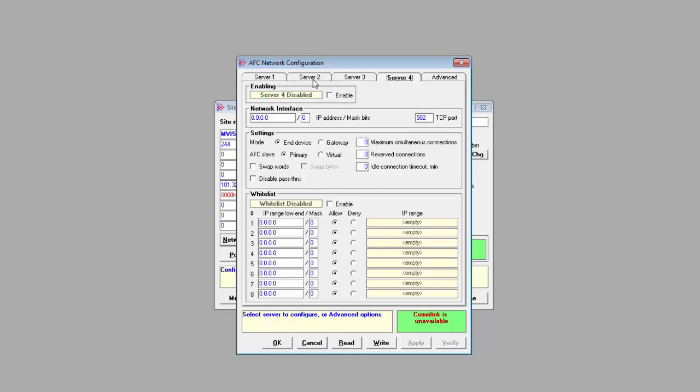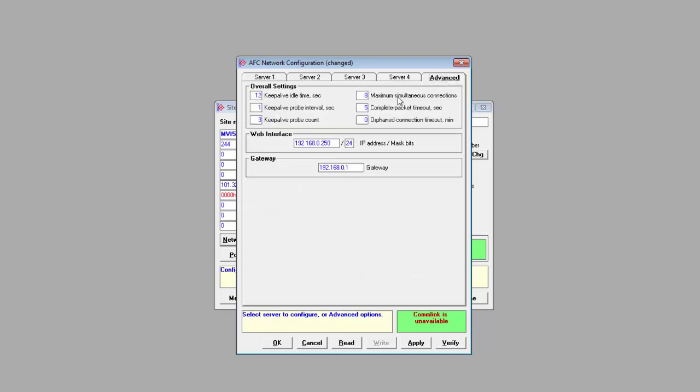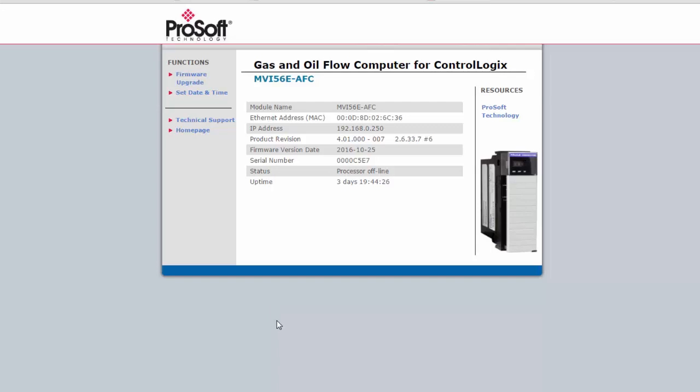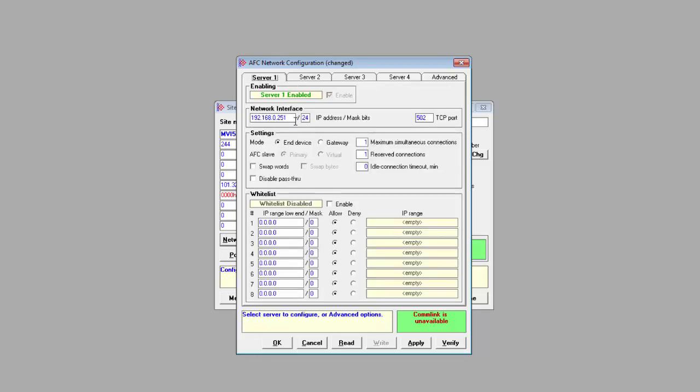Port 502 is the standard Modbus TCP port. We have different module settings and whitelist options as well. At the top you can see there are four server tabs. These allow you to set different configurations up for four servers. So if you do have multiple configurations, you can just select the tab and check Enable. The Advanced tab contains more advanced web options. The web interface you see here is a different address than the network interface. This is used for direct access to the module for firmware updates, viewing module information, and so forth. One important feature that we will use is the orphaned connection timeout. By setting this to any number other than zero, the module will maintain its current connection even if the connection parameters have been changed in the configuration. And we'll use this to change the network IP address to what we want to use in our application, but only once we've made an initial connection to the module using the default IP. So we'll return to this later.